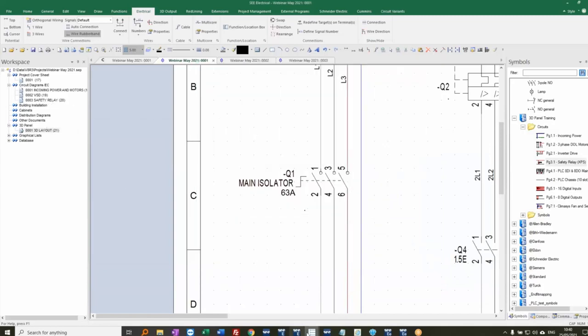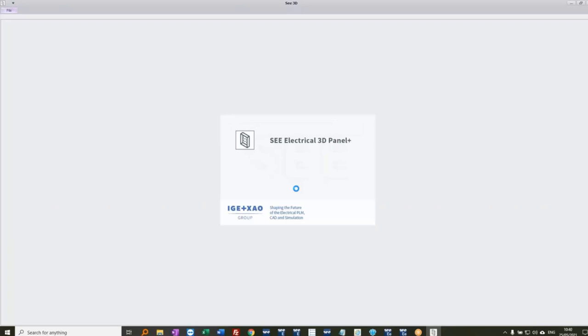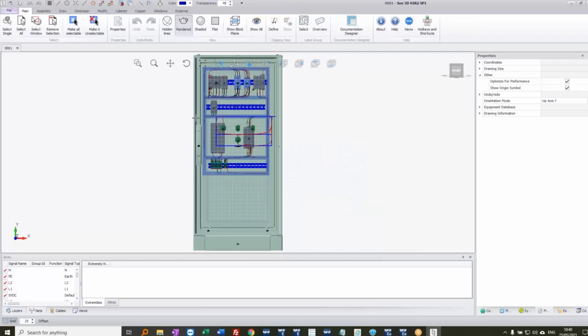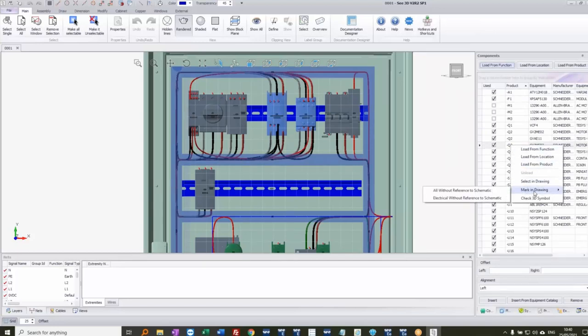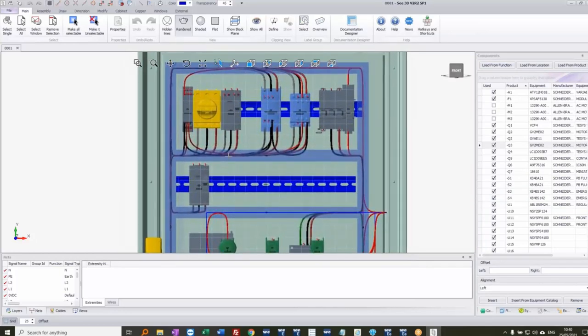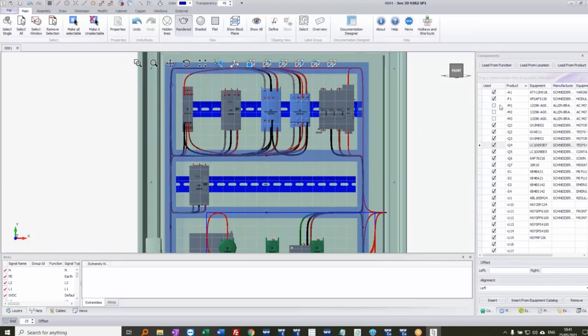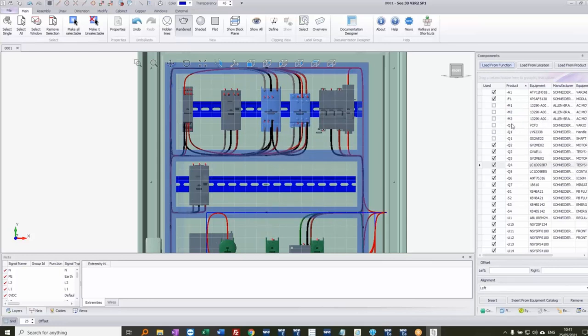Going back into the 3D view, I still have the original switch. In the component list, I can right-click and choose to highlight anything in the drawing without a reference, or anything electrical without a schematic reference. I can see the old disconnect switch is no longer in the schematic. I'll remove it and click 'Load from function' to refresh the component information, and the new VCF3 now appears in the list.